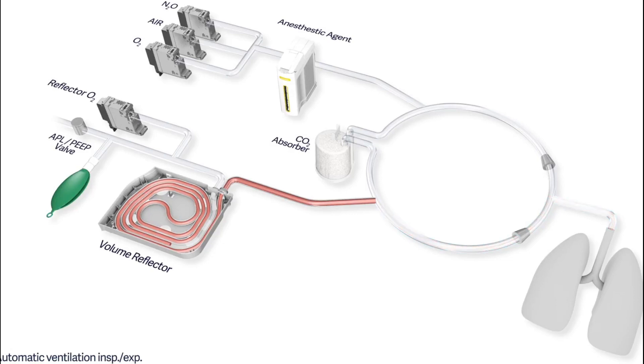A circle system can be semi-closed or closed. In a semi-closed circle, the APL valve is opened and allows excess gas to be removed from the system and reduce the risk of barotrauma.